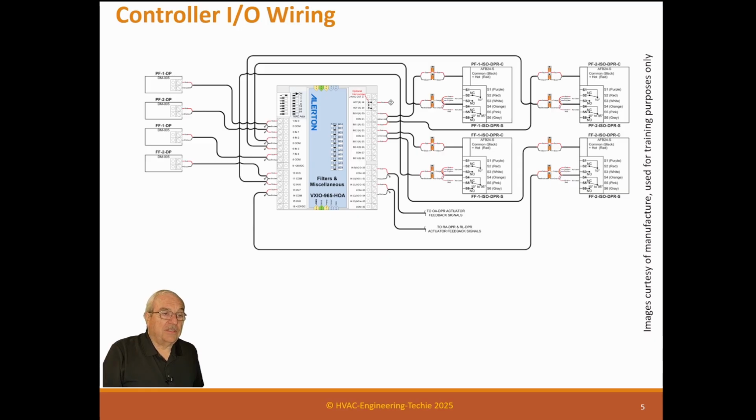All right, so now this is a diagram of a controller, and this happened to be a job I did a submittal review on the other day. I thought, man, this control contractor really did a great job on his submittal, so I lifted his submittal page. This is really a well laid out diagram. It shows the field guy how to wire every single thing. If you notice real carefully, these are all color coded.